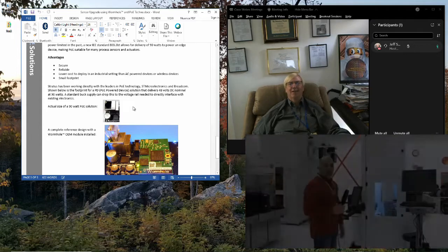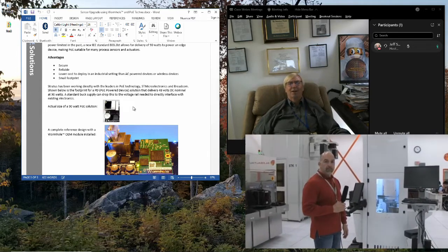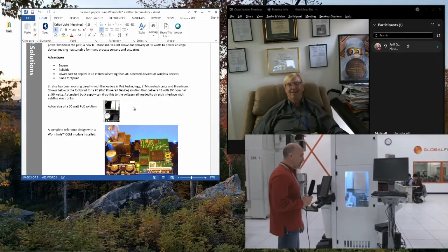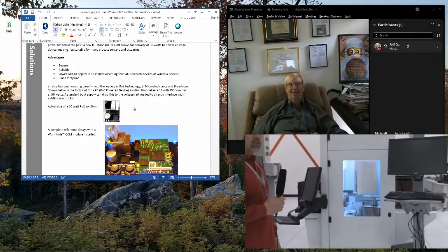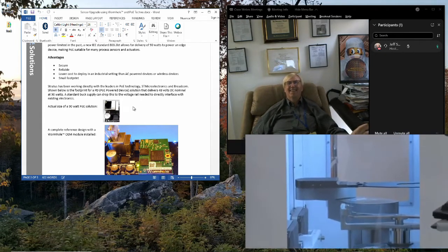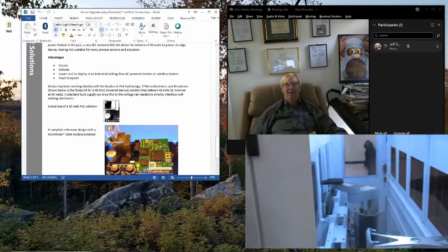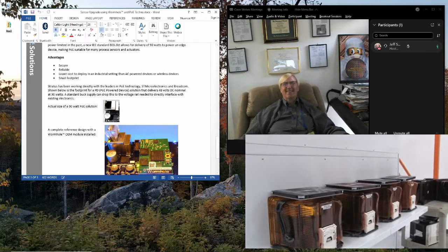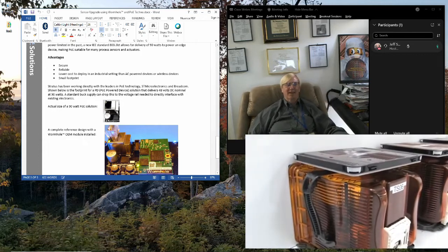You can have up to 59.9 volts. We run nominal up to 60 volts. And the limitation here is class 2 wiring is 60 volts according to UL. So under 60 volts, you can staple the wire to the wall. Look at the network in your office building. It's air wired, tied to the wires holding your drop ceiling. If you bought the low bidder, best case it's in a bundle in some cable tray up above the ceiling.